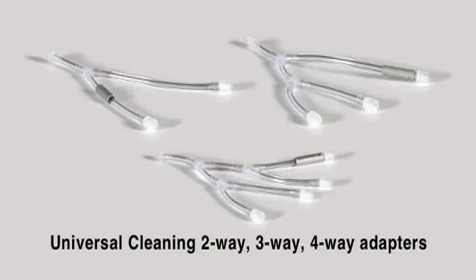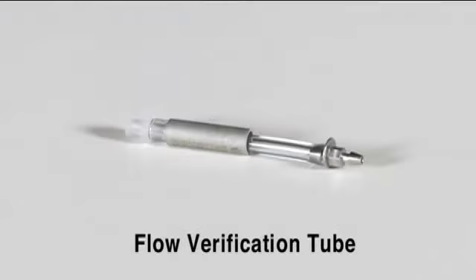Universal Cleaning 2-way, 3-way, or 4-way adapters. These multi-way cleaning adapters will connect to an endoscope's channel irrigation tubing. Selection of whether to use a 2, 3, or 4-way adapter depends on how many connection ports will need to be reprocessed. Flow verification tube. This tubing segment, attached to the Universal Cleaning Adapter extension line, is used during the daily quality assurance test to ensure Scope Buddy is delivering the proper amount of fluid.